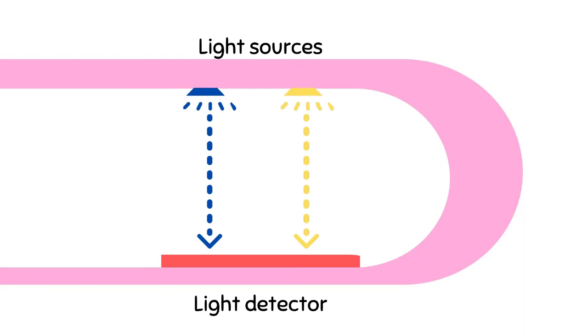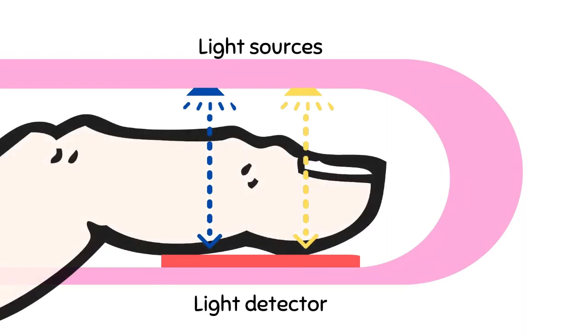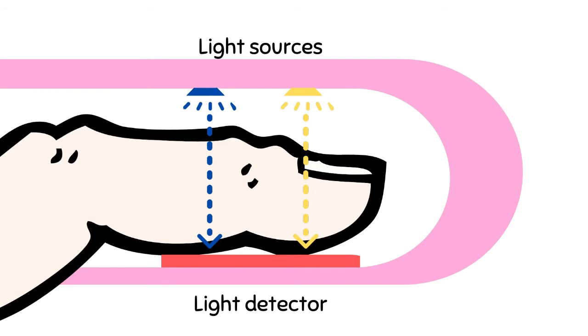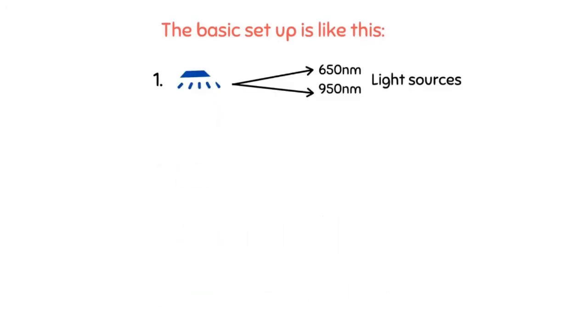We also need a detector that will detect these two lights that come through the tissue of, say, our finger from the two light sources. The basic setup is like this: a 650 nanometer LED light source, a 950 nanometer LED light source, and a detector that detects both lights coming out of the tissues.